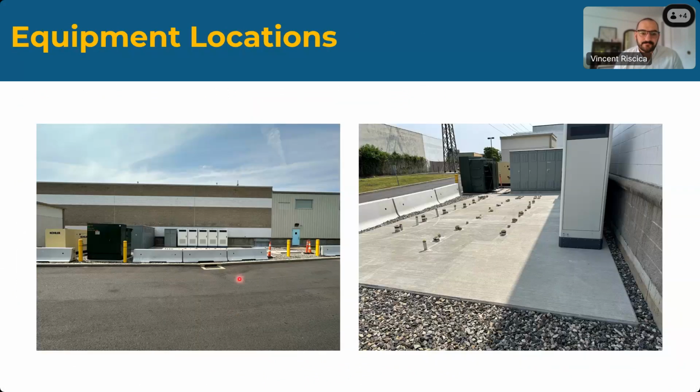That's a very good point. All of this equipment needs front and the switchboards need front and rear access. So minimum 3 feet, more like 5 to 6 feet. And the chargers, depending upon the charger manufacturer, will need ventilation requirements, top, front, and potentially back. These particular ones needed very little in the back, but there is definitely space requirements around this equipment. So that's a good point, Benny.